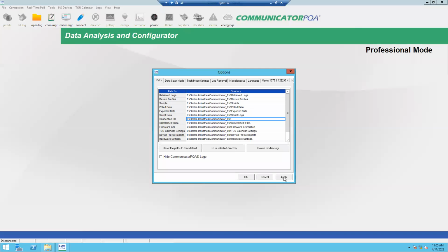But the other thing you can do is set up some automatic report exporting and such, which may be another meeting to go over. But that might be an easier way because you probably just want pieces of data. You'd probably just want, let's say, consumption, kWh. Yes. You probably wouldn't want all the power quality stuff. That usually is only if something happened, then you want to be able to go look at what happened.